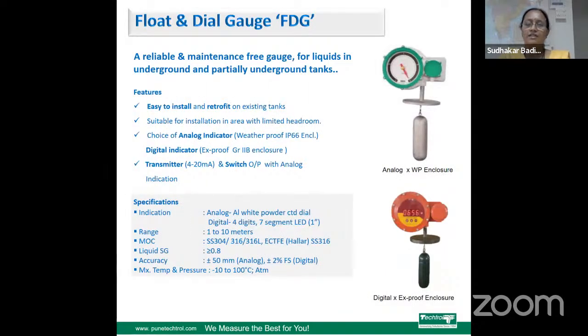The next one is a float and dial gauge, that is FDG. This is a reliable and maintenance-free gauge, designed for underground and partially underground tanks. The gauge is very easy to install and retrofit on an existing tank. It is most suitable for installation in areas where the headroom is limited. Two indicator choices are available, analog and digital. The analog indication is available in a weatherproof enclosure and digital in a flameproof enclosure. Transmitters and switches can also be integrated with the analog enclosure. In digital indication, you will get 4 to 20 milliampere output by default.